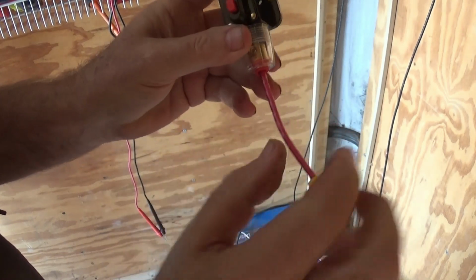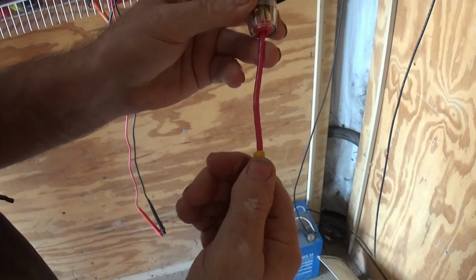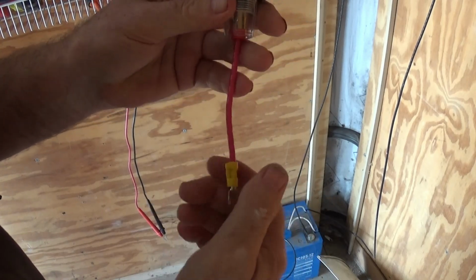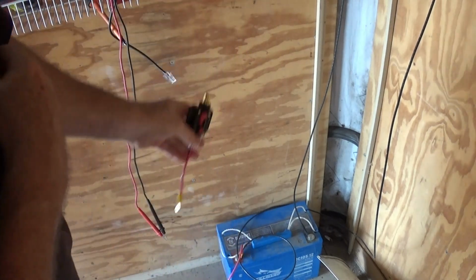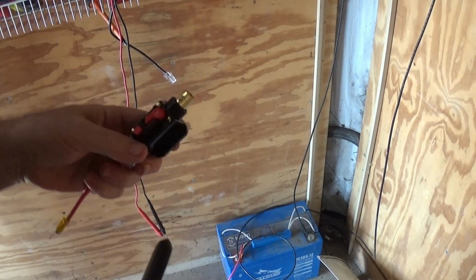This is 10 gauge, so it's perfectly capable of carrying 30 amps with hardly any voltage drop for this short distance, about 4 feet. There's a chart I'll show you, and I'll put a link in the description, that tells you the voltages, wire gauges, and amperage needed for the distance of wire, so you don't lose too much voltage. You get a voltage drop across your wire distance if it's too thin, and you lose that to heat as the electrons dissipate. So the thicker the wire, the less heat will dissipate.